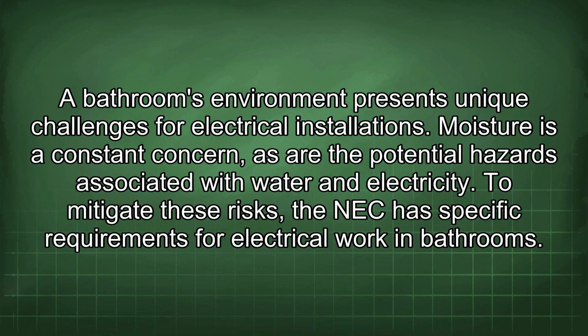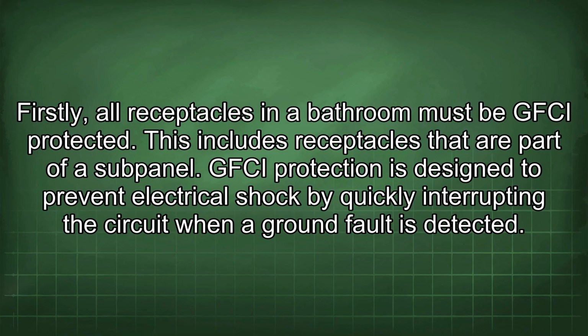Moisture is a constant concern, as are the potential hazards associated with water and electricity. To mitigate these risks, the NEC has specific requirements for electrical work in bathrooms. Firstly, all receptacles in a bathroom must be GFCI protected. This includes receptacles that are part of a subpanel. GFCI protection is designed to prevent electrical shock by quickly interrupting the circuit when a ground fault is detected.